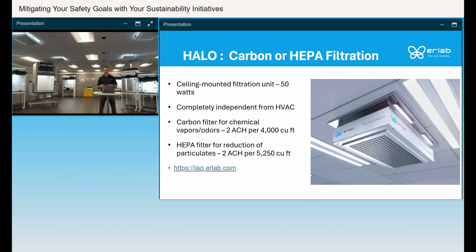And then the HEPA filtered version is for particulates. There's less resistance through the HEPA filter, so you have a higher CFM at about 175. So you need 1 for about every 5,250 cubic feet of space to add the 2 air changes per hour.